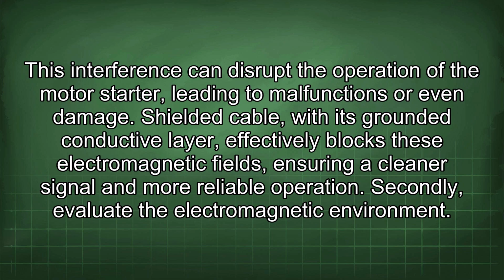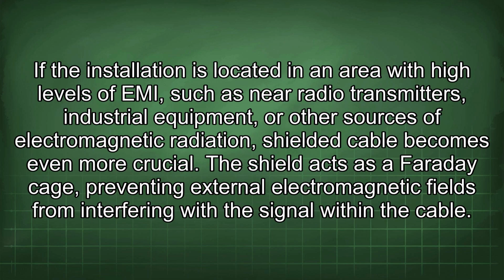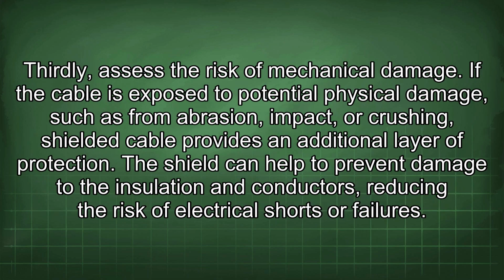Secondly, evaluate the electromagnetic environment. If the installation is located in an area with high levels of EMI, such as near radio transmitters, industrial equipment, or other sources of electromagnetic radiation, shielded cable becomes even more crucial. The shield acts as a Faraday cage, preventing external electromagnetic fields from interfering with the signal within the cable. Thirdly, assess the risk of mechanical damage. If the cable is exposed to potential physical damage, such as from abrasion, impact, or crushing, shielded cable provides an additional layer of protection.